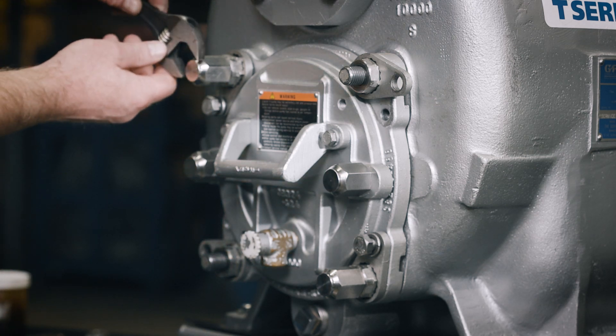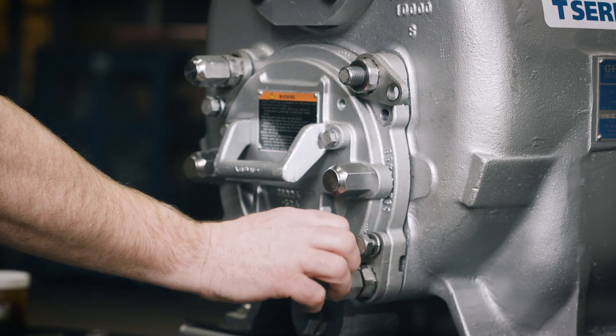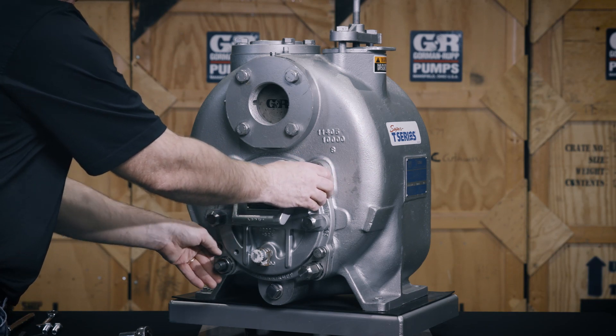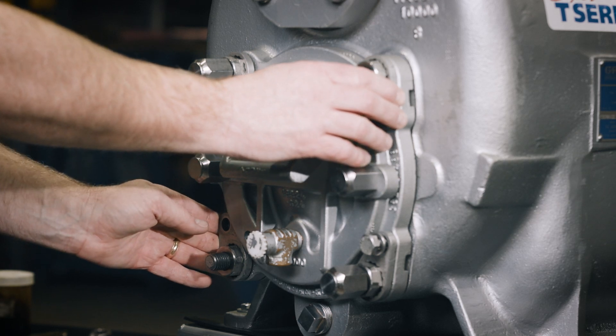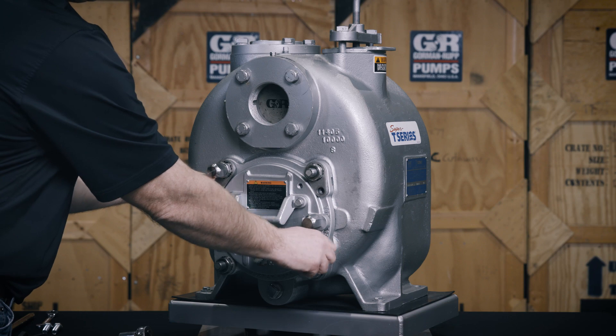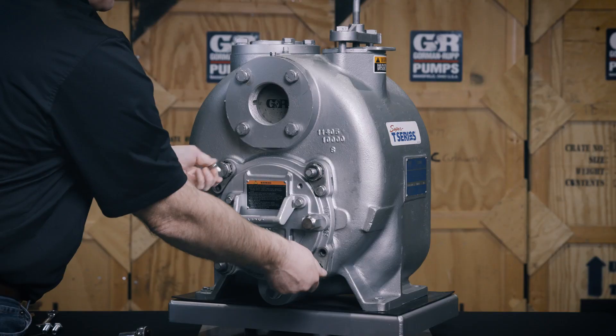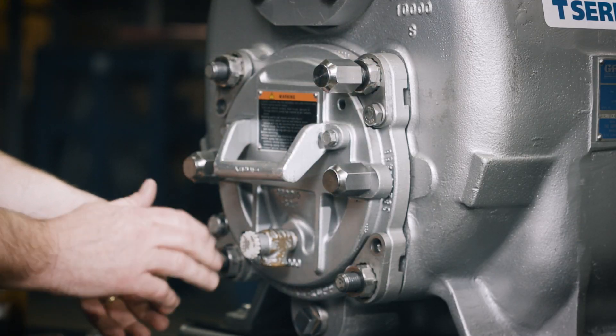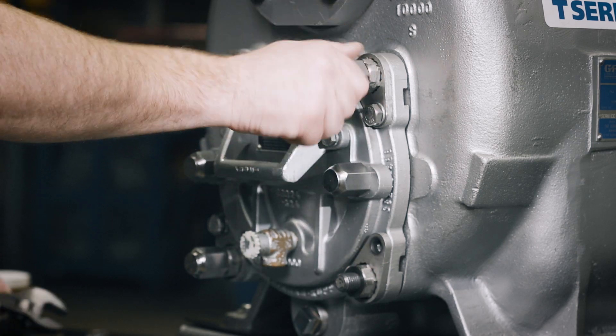Loosen the back cover nuts at the 10 o'clock and 4 o'clock positions, maintaining the zero face clearance. Rotate the locking collars at the 1 o'clock and 7 o'clock positions clockwise until the holes in the locking collars realign with the holes in the cover plate. Transfer and tighten the locking collar cap screws and back cover nuts from the 10 o'clock and 4 o'clock positions to the 1 o'clock and 7 o'clock positions. This will hold the face clearance at 15 thousandths of an inch.